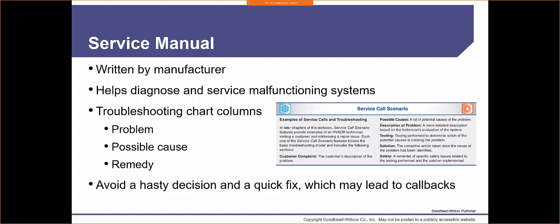Avoid a hasty decision and a quick fix, which may lead to callbacks. That's one thing that we don't want in our industry, is callbacks. Callbacks are when you came to a site and you did a repair, and then the customer calls back stating that the repair didn't work. Sometimes it's going to happen. Sometimes there's another issue with the system we couldn't catch until we made that first repair. So for example, we come to a site and it's a no heat call. We go in there and we see that our air filter is completely plugged up. So we replace the air filter with a new one, it fires up and it runs. Great. Now we say, hey, hallelujah, we're good, we can just leave.